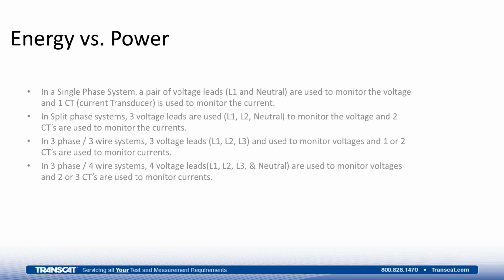And then if we were in a 3-phase, 4-wire, or sometimes 3-phase, 5-wire system, we would need 4 or 5 voltage leads to measure the 3 phases, reference to the neutral, and possibly also reference to a ground. And that would give us our voltage monitoring. And then we would need 2 or 3 of these current transducers to be able to properly measure all the currents.